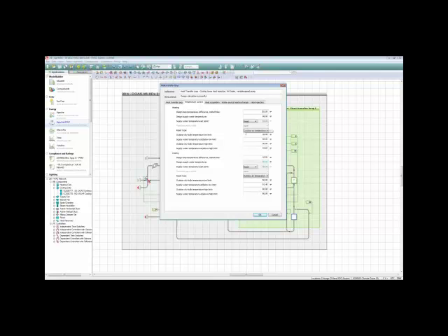So in other words, I can size the loop capacity and flow rate for a design temperature of, in this case, 10 degrees Fahrenheit for heating, and then I can say, well, actually, I want to control that either with an outdoor reset, or I want to have some constant value where I'm going to control it to, say, something much higher, warmer, or something like that.